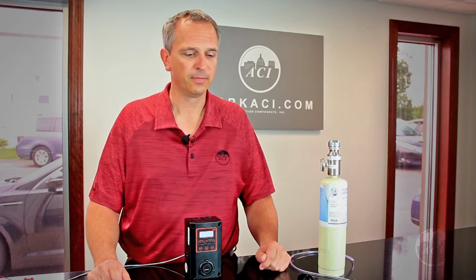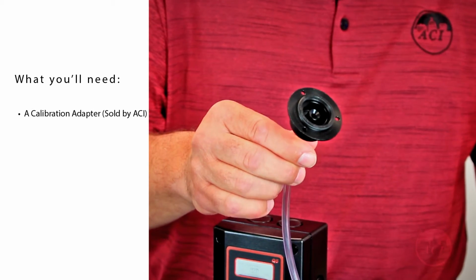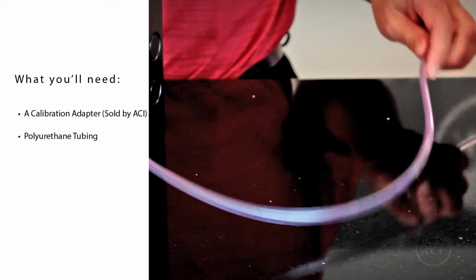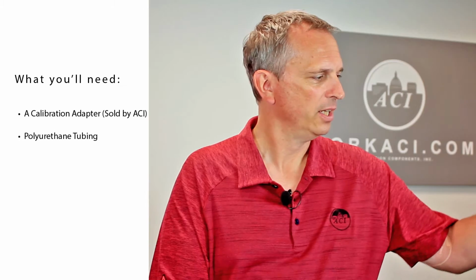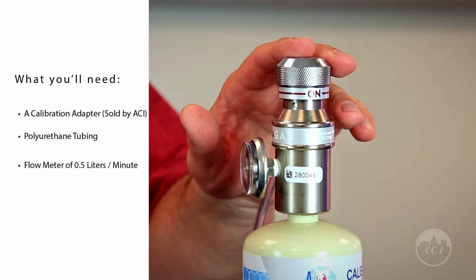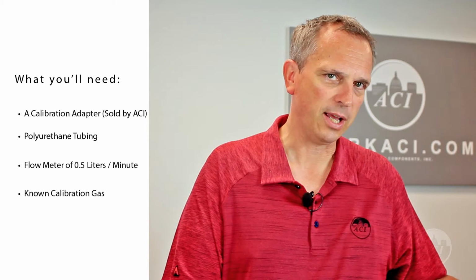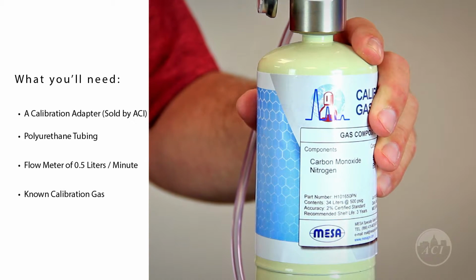While you're doing this bump test, and that's what it's called, you can check the functionality of the whole system. Because what we're doing is we're going to be checking to make sure that the relays trip. The first relay could be set to open up an exhaust fan. The second relay could be a fresh air intake. So we're checking the whole functionality of the system, make sure everything works. So what you need is going to be the calibration adapter, some polyurethane tubing, a flow meter of 0.5 liters per minute, and a known calibration gas that is not expired.